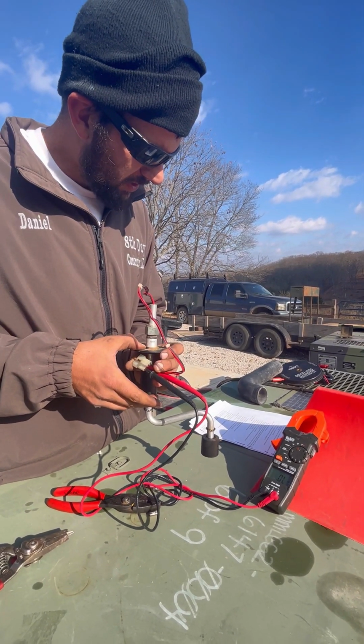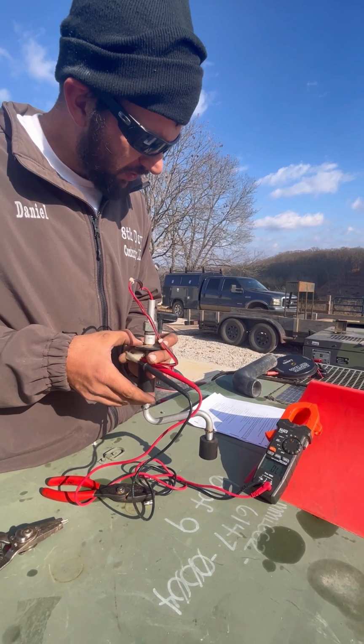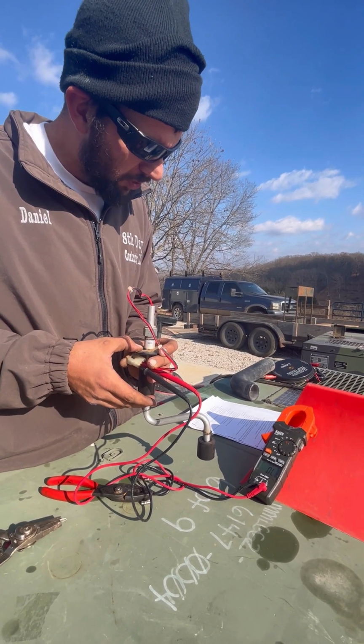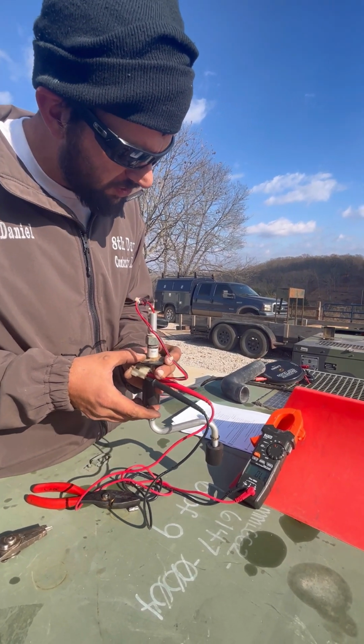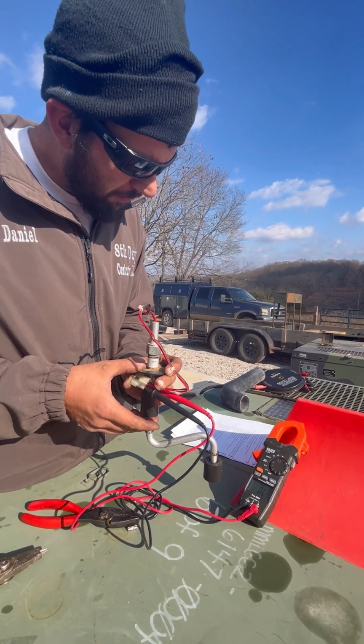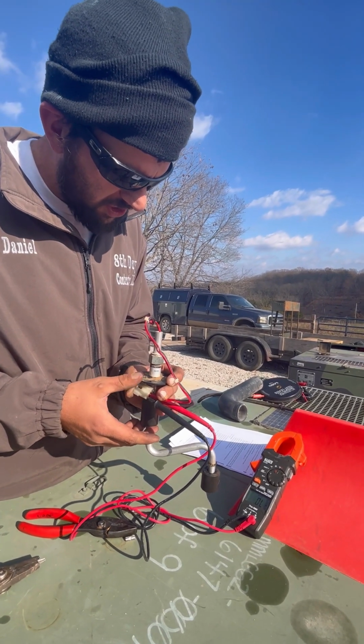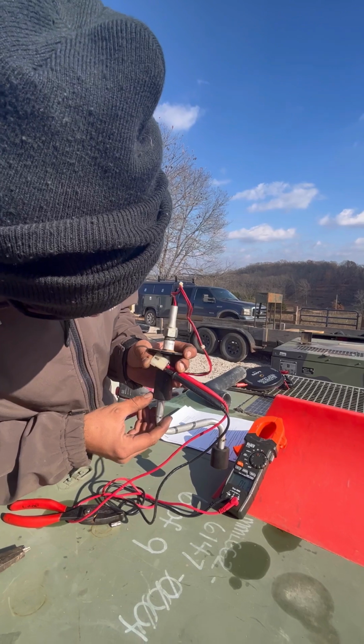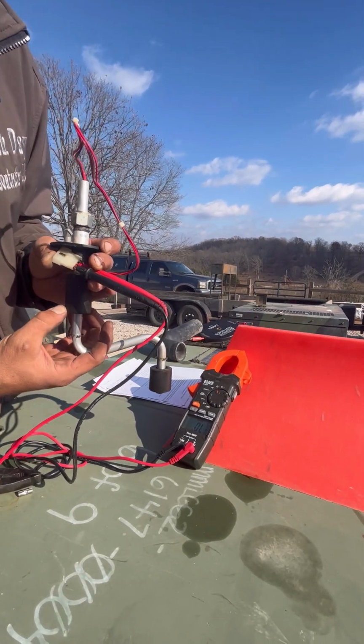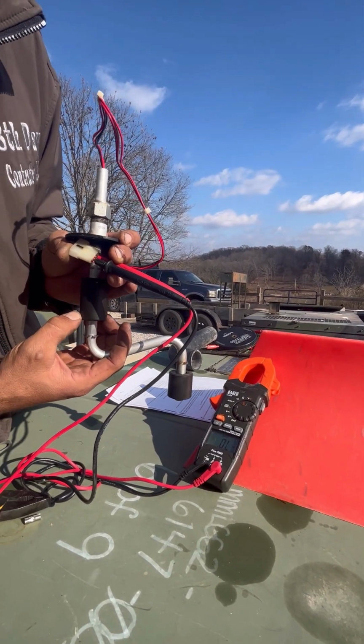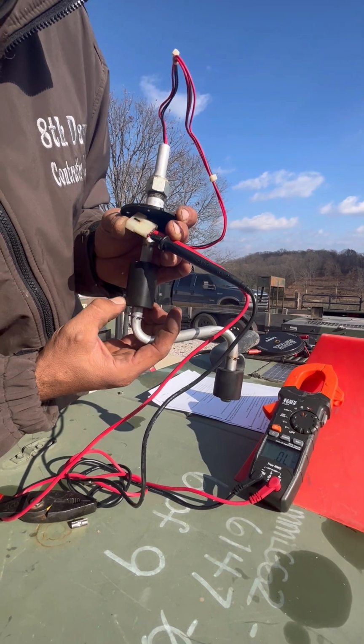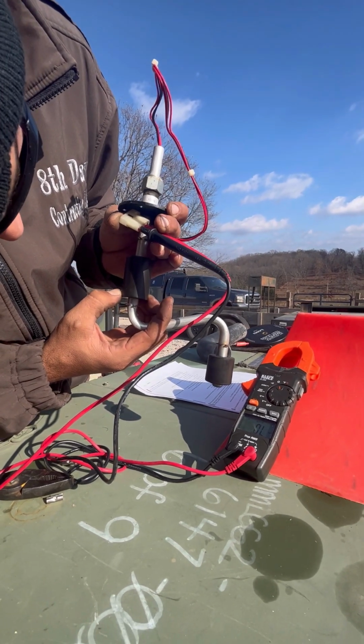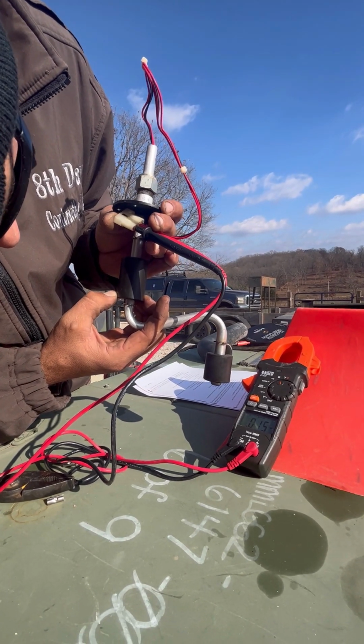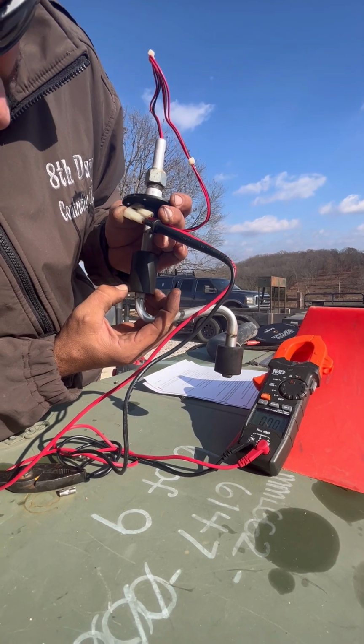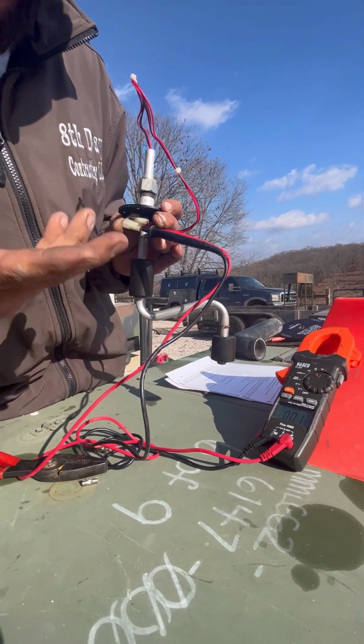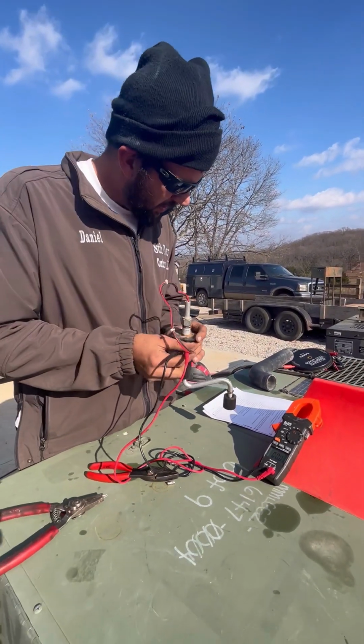Okay. It says with the upper float towards the down position, multimeter should indicate continuity a quarter inch before the float reaches the down position. So we're going to move this float down. You can see and I'll tell you right when we're about a quarter inch, which is about right there. It's about a quarter inch. And we started continuity all the way down. So the upper's working properly.